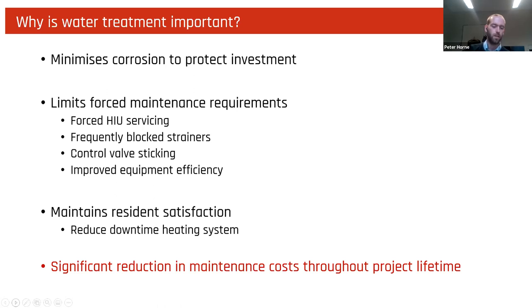I have seen in the last couple of months actually a plant room with a primary valve sticking, which dramatically reduced the plant room efficiency of your boilers due to high return temperatures. It's just not controlling very well. And then the knock-on effect to that was increased tariffs, resident discomfort, poor resident satisfaction.